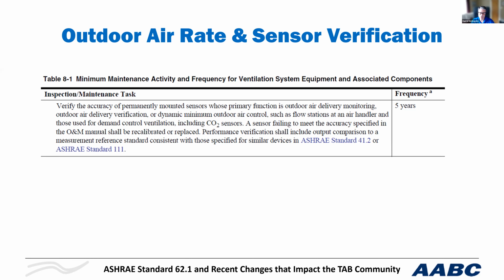Pressure transducers are going to drift. The extent of the drift is going to depend on the original accuracy, the span of the transducer, and the environment it's in. A pressure transducer outside, because of the extreme temperature ranges, is going to drift a lot faster than a pressure transducer inside. And CO2 sensors, for example, are responsible for demand control ventilation. Although most of them have background calibration these days, their calibration is to a single fixed point, typically 400 parts per million. And they are also affected by temperature and pressure. So these things have to be calibrated on a regular basis.